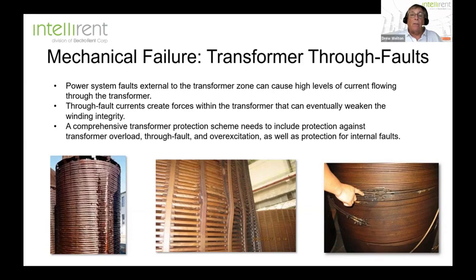Now, there are a number of reasons that you have mechanical failure in transformers. And the one we always think about is, of course, transporting. You transport that transformer from the factory out into the field and you get ready to commission it. And you might do an SFRA test to make sure that no winding deformation or buckling or anything like that happened during the transportation. But you can also get this type of mechanical failure from seismic activity. Maybe if it's a GSU where you have improper synchronizing, it creates a lot of mechanical stress on the windings. But the one that I think is most overlooked is through faults.